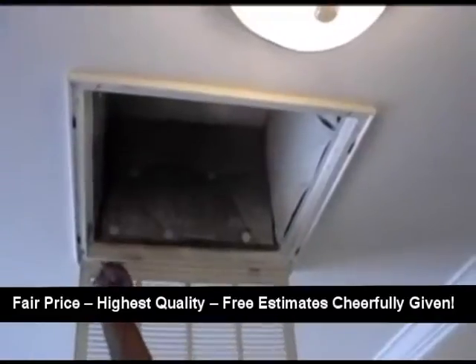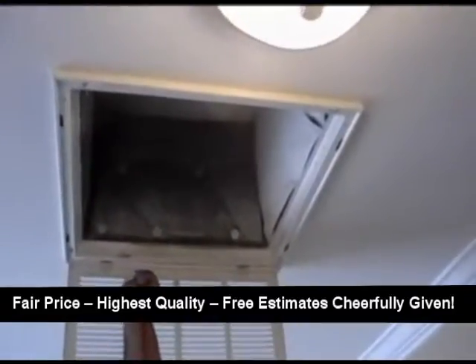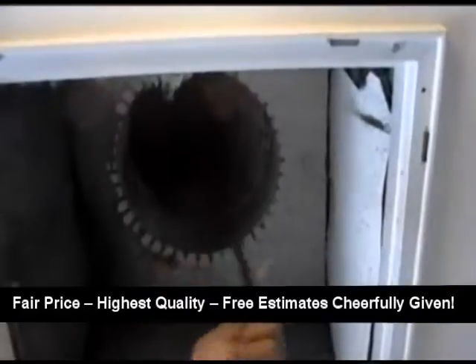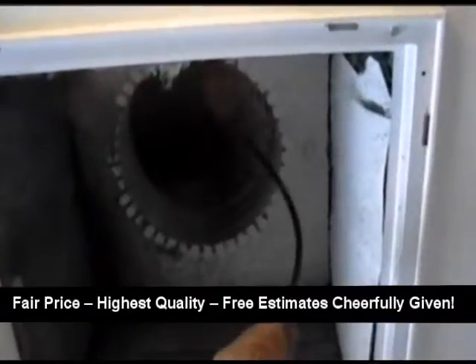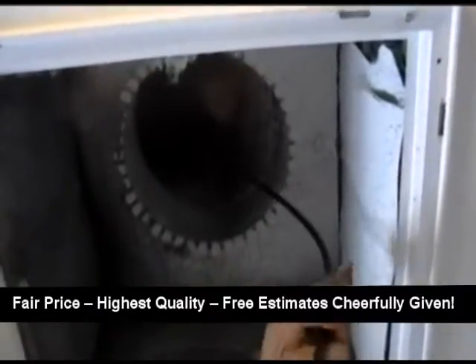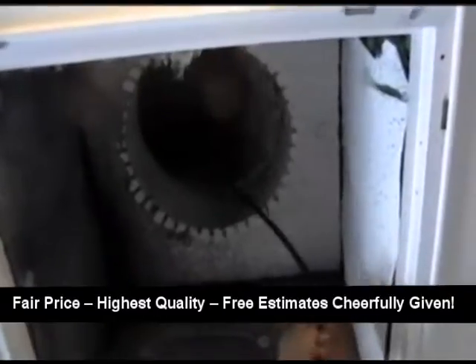Once all the vents are completed, then we disconnect and we hook up to the return side of the system. The return side is where you put your filter at. We do this side separately because we don't want to draw anything through the return side through the coil of the HVAC unit. But it will be done the same way. Negative pressure on one end, coming through the other end with positive pressure, pushing everything towards the negative air line.